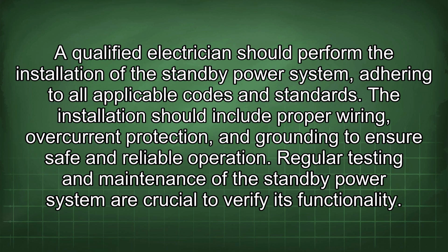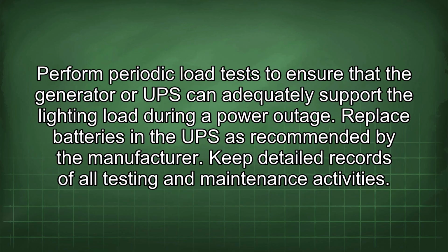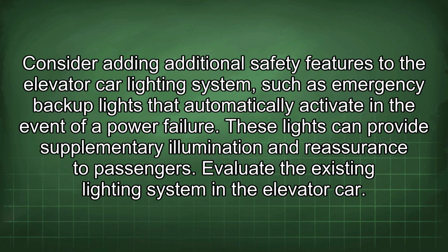Regular testing and maintenance of the standby power system are crucial to verify its functionality. Perform periodic load tests to ensure that the generator or UPS can adequately support the lighting load during a power outage. Replace batteries in the UPS as recommended by the manufacturer. Keep detailed records of all testing and maintenance activities. Consider adding additional safety features to the elevator car lighting system, such as emergency backup lights that automatically activate in the event of a power failure. These lights can provide supplementary illumination and reassurance to passengers.